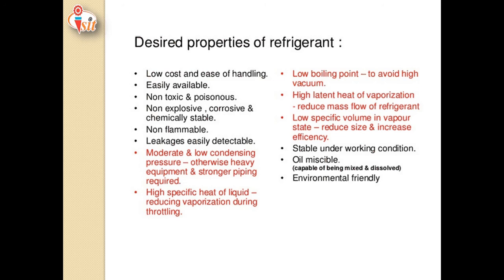The refrigerant should have moderate and low condensing pressure; otherwise heavy equipment and stronger pipes are needed. It should have a high specific heat of liquid, thereby reducing vaporization during throttling. A very important property is a low boiling point to avoid high vacuum — for example, ammonia has a boiling point of minus 33.33 degrees Celsius. Another important property is high latent heat of vaporization, which reduces the mass flow rate of refrigerant.